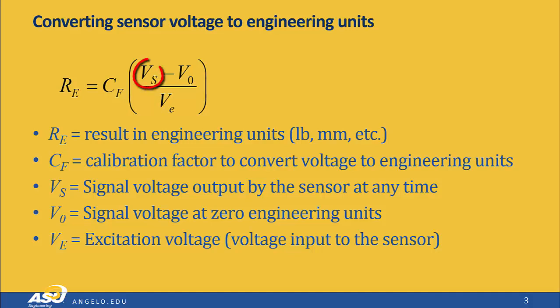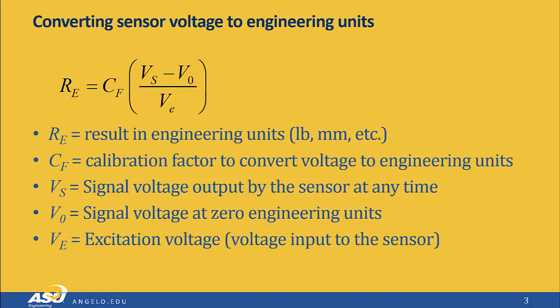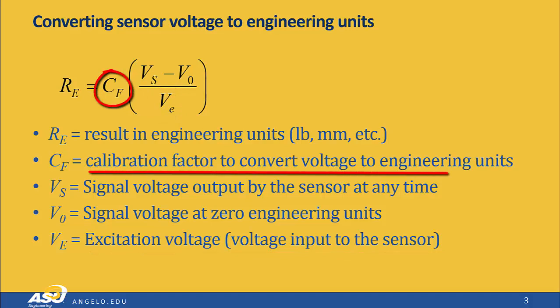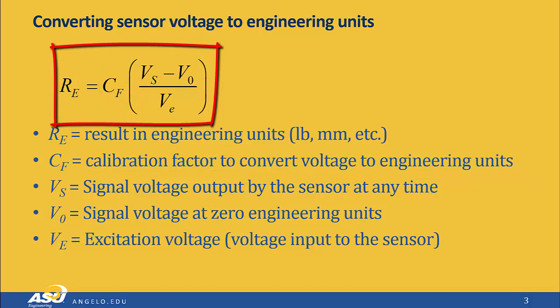To do that conversion, we take V_S, the actual signal voltage put out by the sensor, subtract V_0, which is the signal voltage at zero engineering units — so the signal voltage at zero pounds force or zero displacement. We divide that by V_E, the excitation voltage we put into the sensor. Then we multiply by C_F, the calibration factor that converts the voltage to engineering units. The basic formula is: R_E = C_F × (V_S − V_0) / V_E.